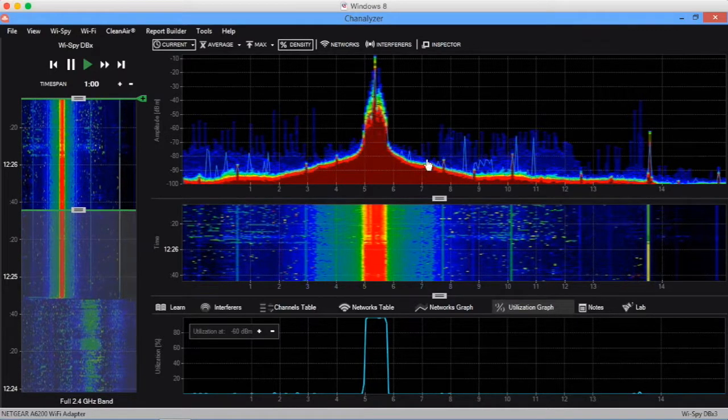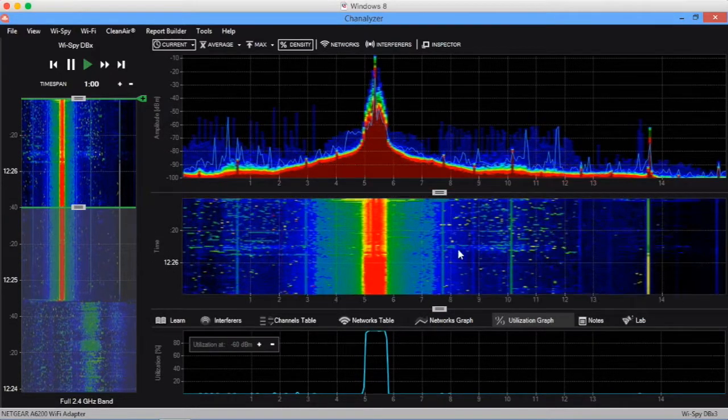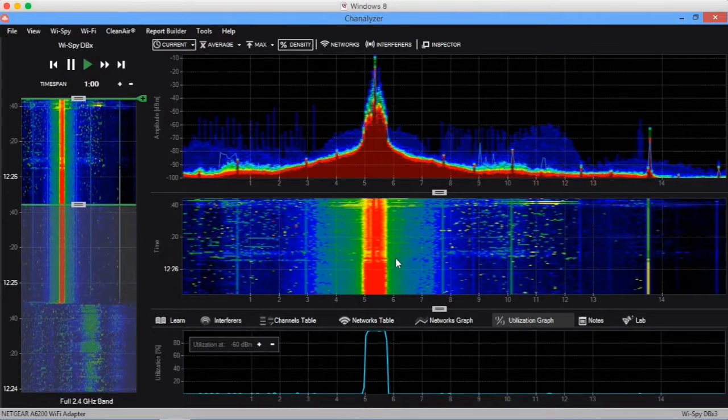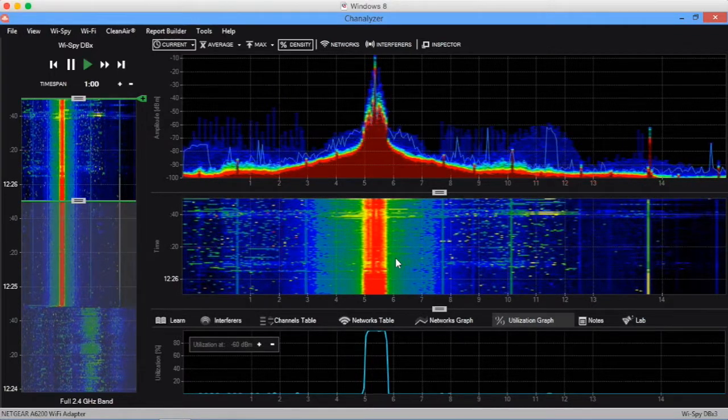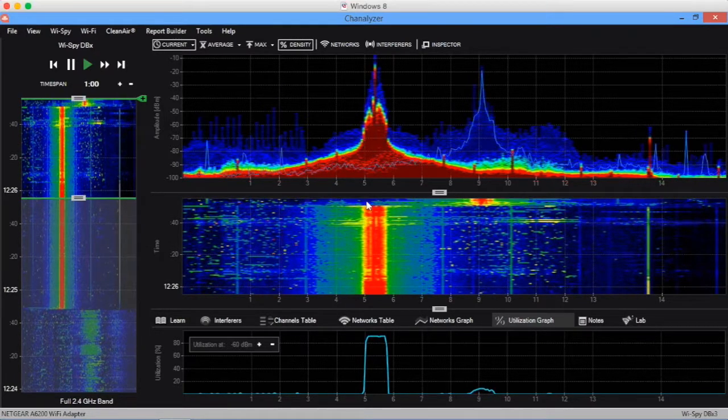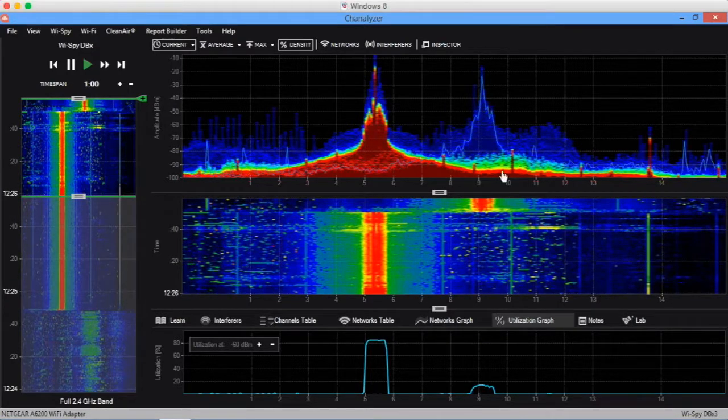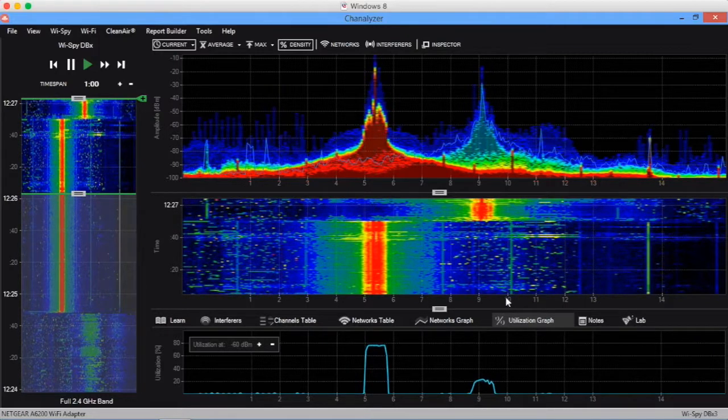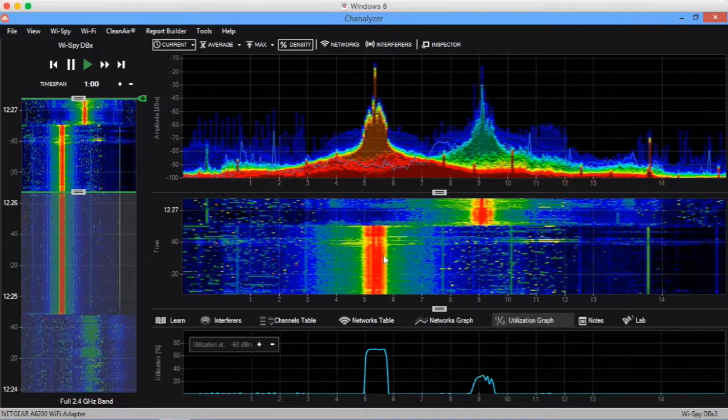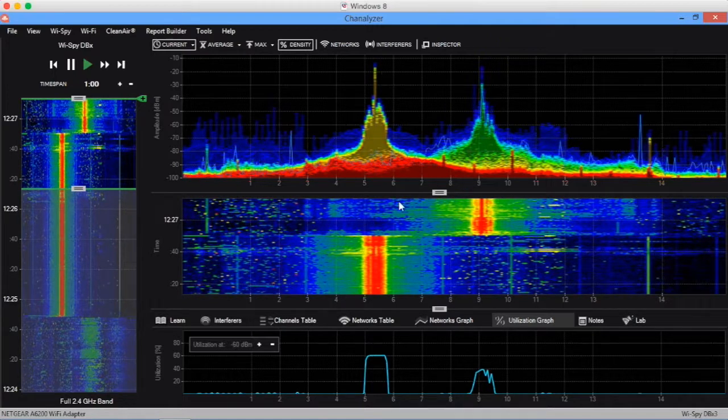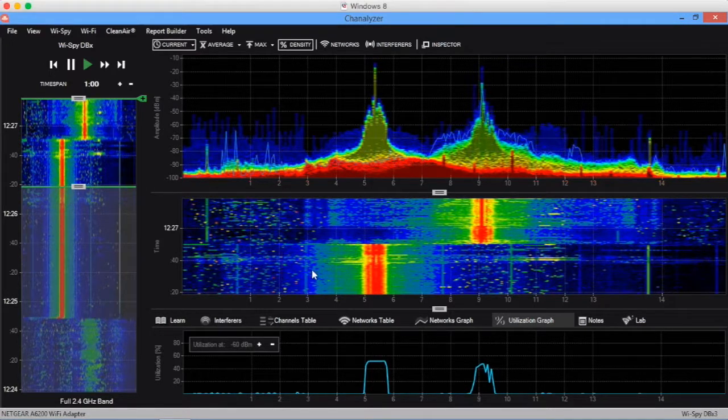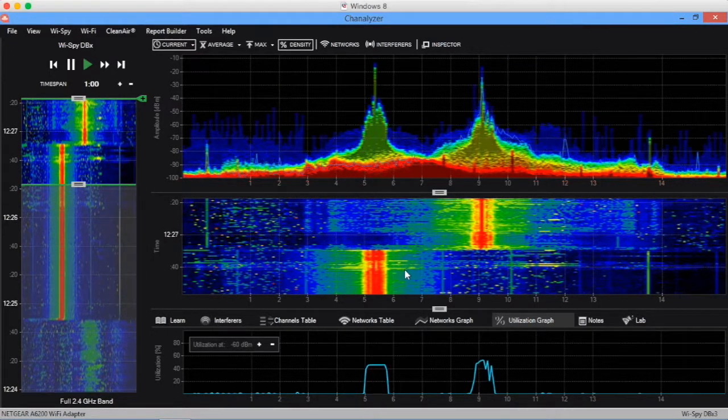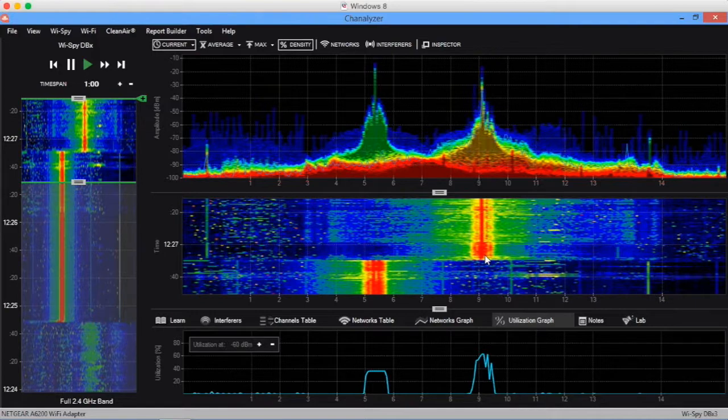The next thing I want to talk about is the waterfall view. The waterfall view shows us what's happening over a period of time, kind of like a seismometer for an earthquake except instead of using scribbles it uses colors. Watch what happens when this device switches to another channel. You'll notice that this red stripe right here stops and then switches over here to about Wi-Fi channel 9. Down here the color doesn't show us the utilization; instead the color shows us how loud something is talking. Notice how this red stripe, the most intense part of the color, corresponds to the loudest part of this signature in the spectrum. As we taper off and go down here, we notice it goes from green to blue and then eventually black. Black means that there was really nothing to report, nothing happened there at all. But we can see that this device switched from one channel to another.